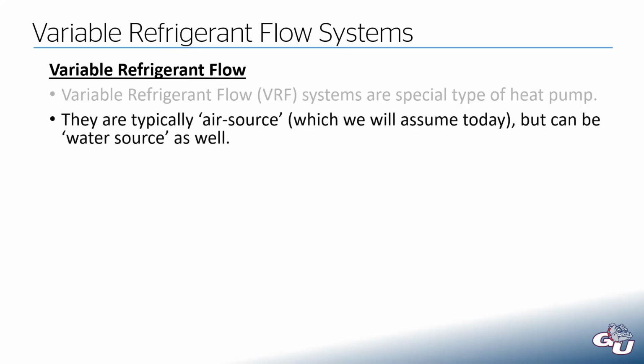VRF systems typically are air source, which, as a reminder, just means that the heat sink or the heat source is just the ambient air surrounding our building. That's where we are either rejecting our heat when we're in air conditioning mode, or that's where we are pulling our heat when we're in heating mode.